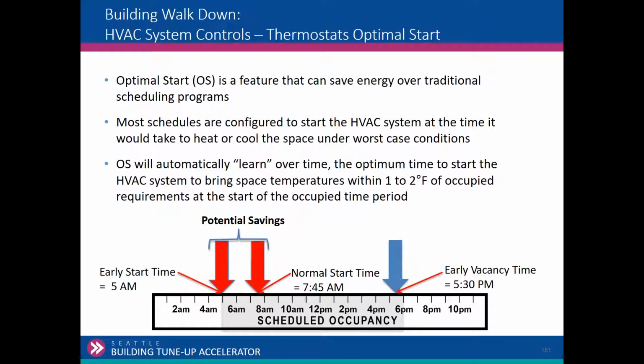This building, by the way, has struggles on really cold days to the point where they're having to override the setback and run it 24/7 to keep it going, which is okay. That happens, but we want you to make sure you go back once it gets milder, once we get past this cold weather, to optimum start. So the potential for savings is basically having the microprocessor determine when to start the HVAC, and then you program the occupancy schedule. So we want to make sure that the programmed occupancy schedule is in there.